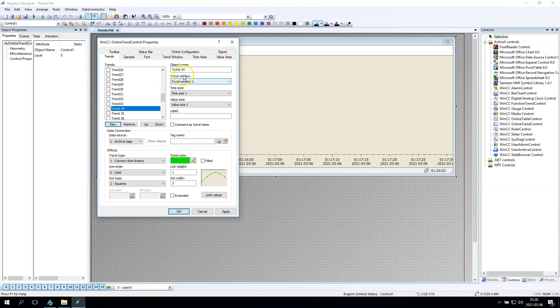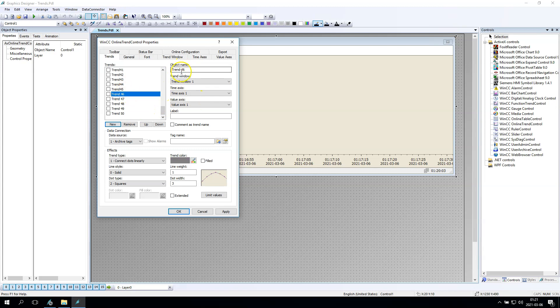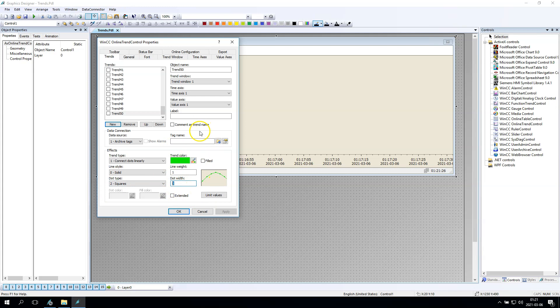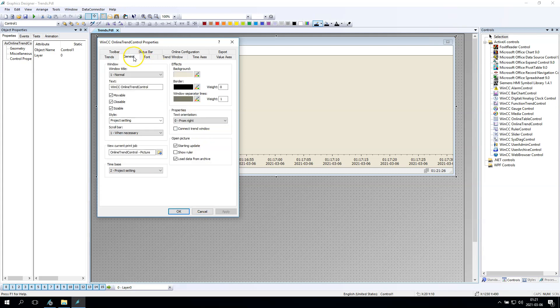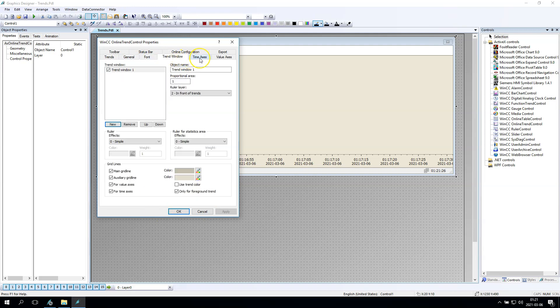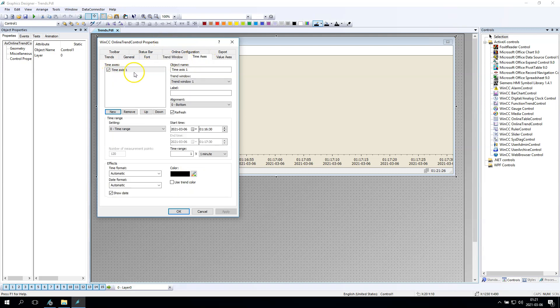I will name these trends just Trend 1 to Trend 50 to make sure my script runs with good numbers, because I will use some internal tags like X, and this X will be from 0 to 50. We are using the archive tags. We have the trend type, line style, dot type, and we can configure all of this manually so you are able to show your analogues on the screen.